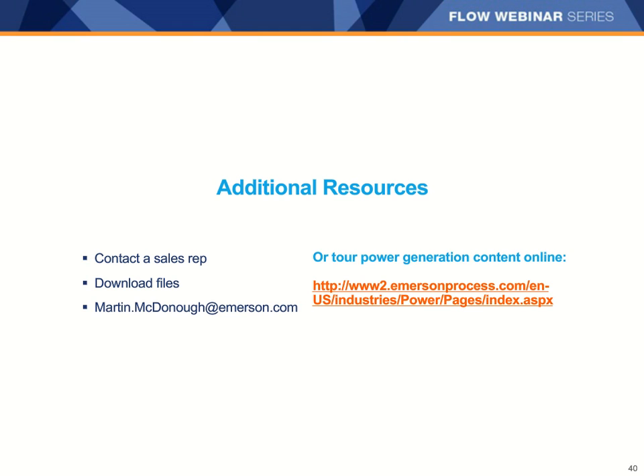Another one here. What temperature limits do you have on the meter? The standard sensors are up to 400 F, and we have high temp versions that go up to 662 Fahrenheit. How many SMV results can be stored in the transmitter? Currently, we can store up to 20 different verification results inside our transmitter that can be downloaded at any time.